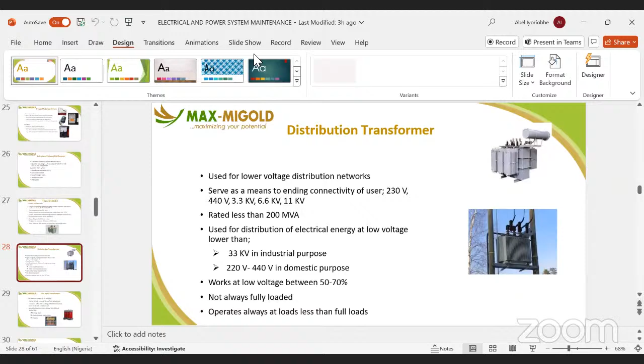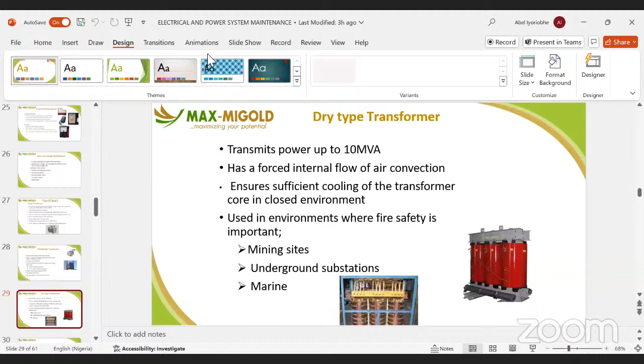So this is a dry type transformer. It does not require any form of oiling or water. It's problem free. What it needs is cross ventilation, so as to eliminate or expel the heat that is being produced. When you go to most of these mounting stations, these are the transformers that you see, because they require less maintenance.